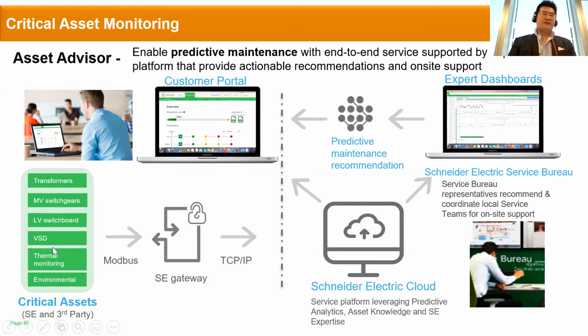Not much in Hong Kong, but in other places like China they have a lot of industrial plants, or in the US they still have a lot of plants. Thermal monitoring, like for the bus bar, especially in some joints with screws, that's the hotspot. You need to monitor the temperature, otherwise it will overheat and it will be gone. Environmental factors like indoor temperature and humidity, and sometimes you need to measure the noise level, air quality, or dust levels. These are all the things we need to monitor.